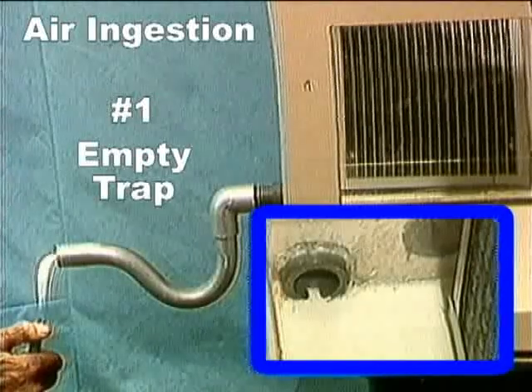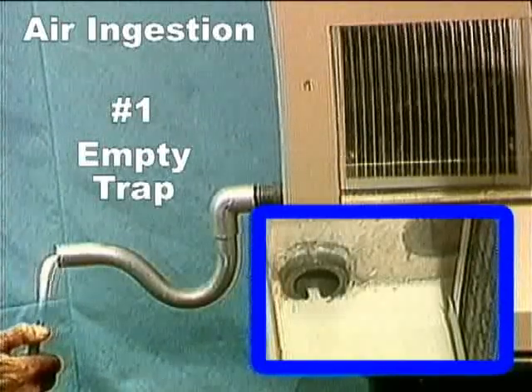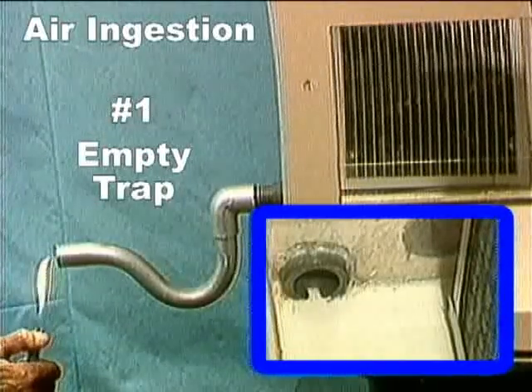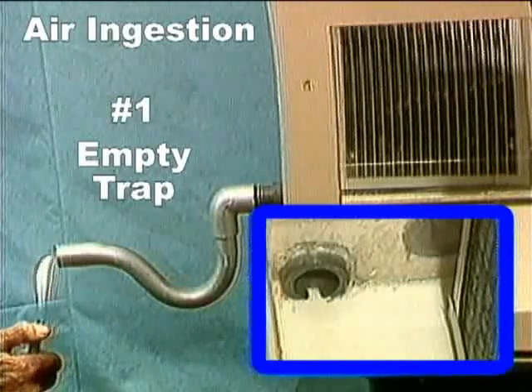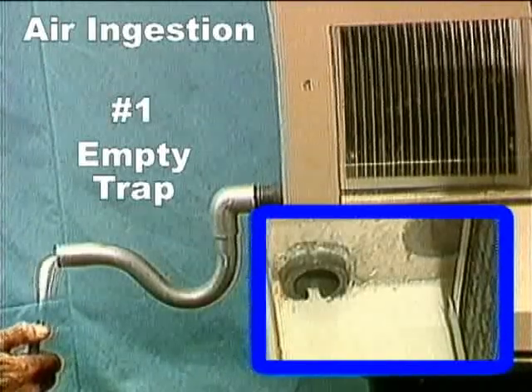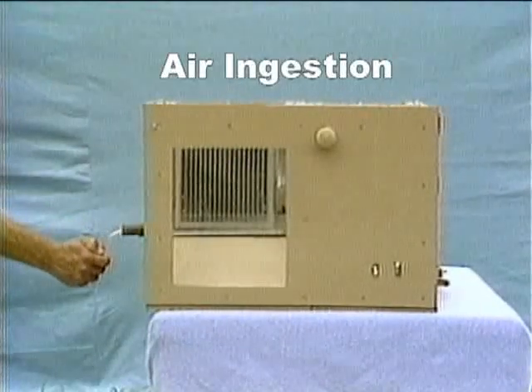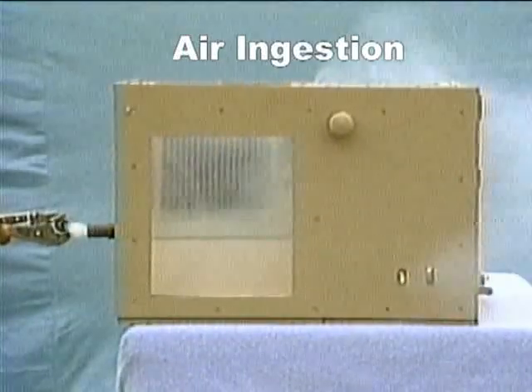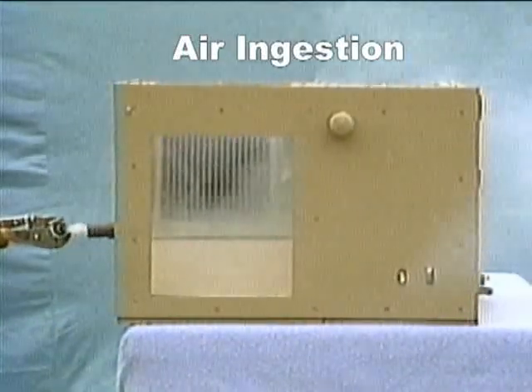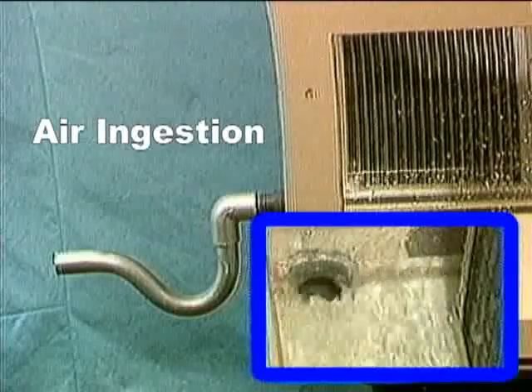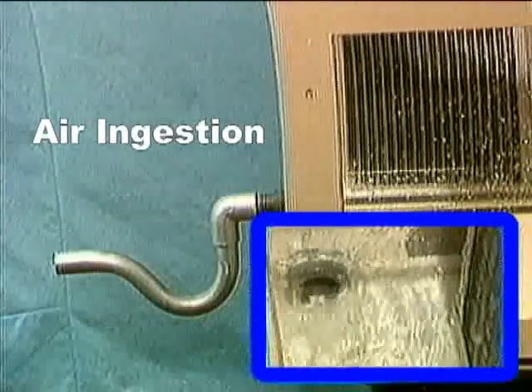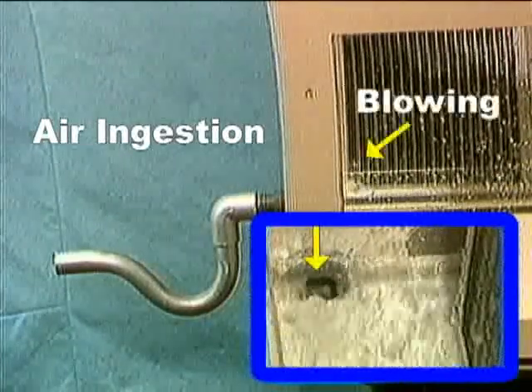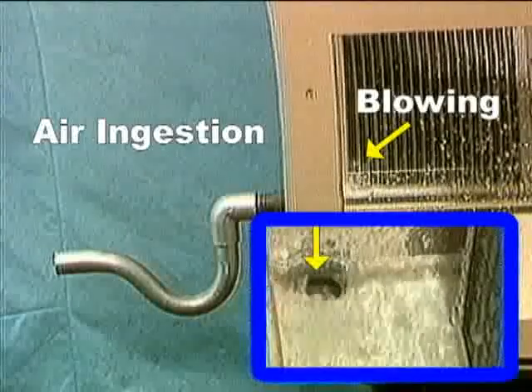The first demonstration shows the effect of operating a system with an empty trap. During startup for summer cooling and during winter operation, the empty trap has no seal and acts like a missing trap, allowing air ingestion. If present, toxic or noxious air near the drain outlet will be spread into the building. This ingestion of air also causes condensate to stand in the pan and leads to condensate blowing inside the air conditioner.